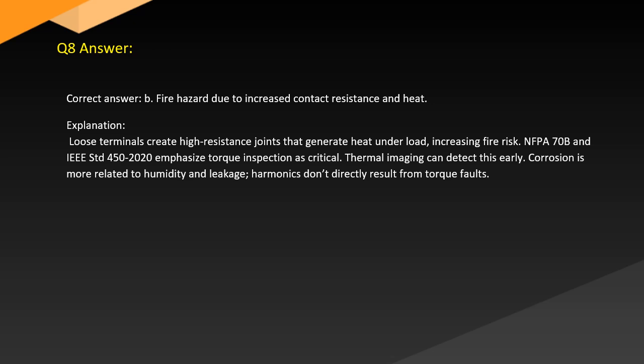Answer. Correct answer: B. Fire hazard due to increased contact resistance and heat. Explanation. Loose terminals create high-resistance joints that generate heat under load, increasing fire risk. NFPA 70B and IEEE 450-2020 emphasize torque inspection as critical. Thermal imaging can detect this early. Corrosion is more related to humidity and leakage. Harmonics don't directly result from torque faults.